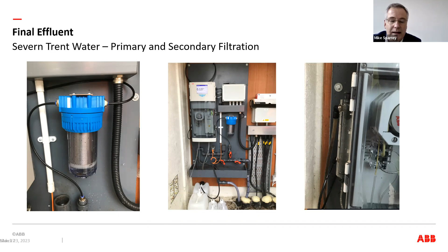This allowed two phases. First, we didn't have to touch the primary filter for at least 3 to 4 months, it stayed clean because it had a greater pore size and was still able to produce sample. Second, the secondary filter allowed up to 2 months before any cleaning was needed, depending on the sample and time of year, since final effluents can vary in solid levels seasonally. On the right you can see a reasonably compliant sample pot, very clean, which meant the instrument just carried on working to its normal maintenance regime.